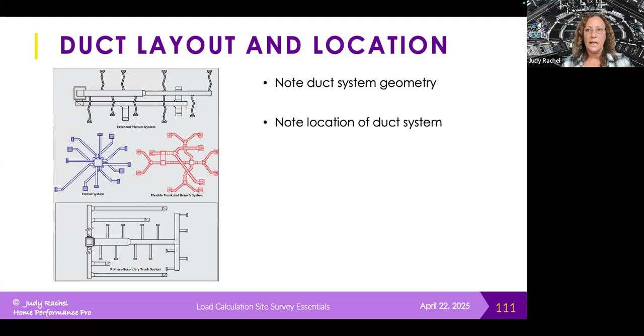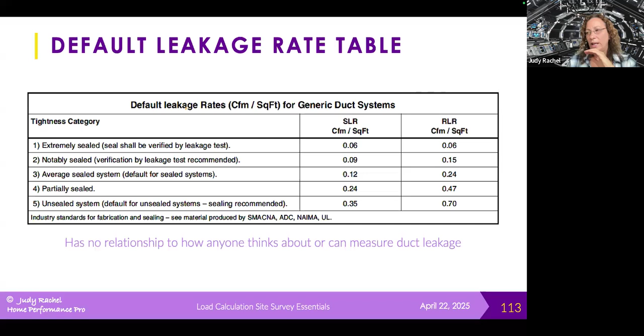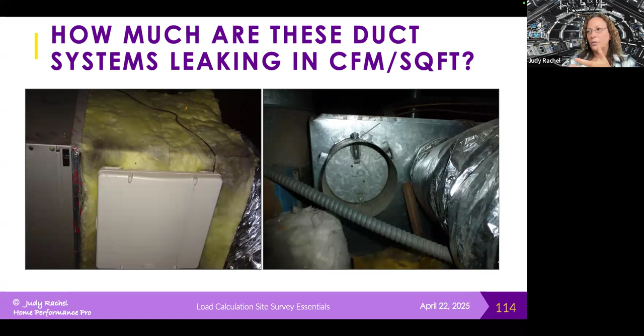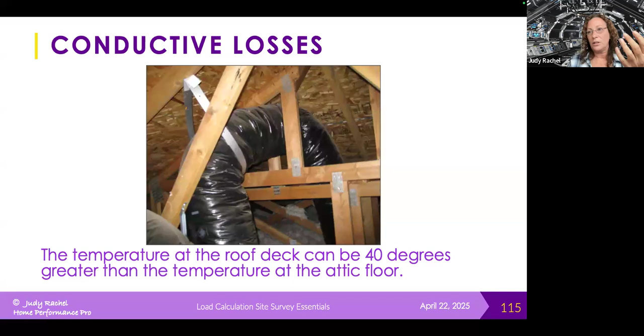Duct loads and data collection challenges. The default for how Manual J was written really has no relationship to the way that anybody thinks about or can measure duct leakage. There's no way to look at a duct system and figure out how many CFM per square foot they're leaking. So really we need to do the duct test. And unfortunately, conductive losses change based on where the ducts are. So if ducts are up by the roof deck, they're going to have greater conductive losses than if they're down by the joists or if they're buried in insulation. And there's not really a good way to describe that.